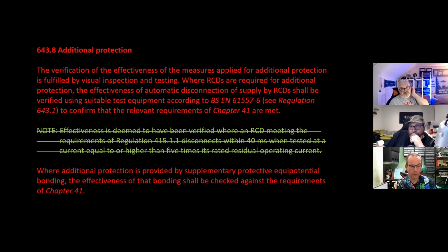So 643.8, additional protection, about verification of the effectiveness of testing of RCDs. Nothing's changed except the note, which has been deleted - the note that said effectiveness is deemed verified when it disconnects within 40 milliseconds at 415.1.1. So the 5 times test is gone. They've deleted it - that's probably Hager and that whole shenanigans with the 250 milliamp 5 times and all the rest of it.